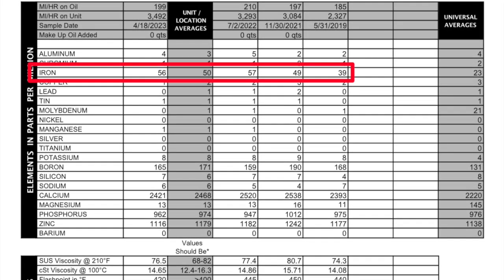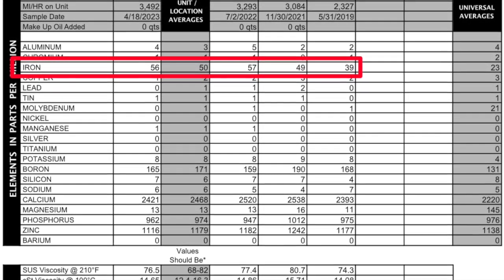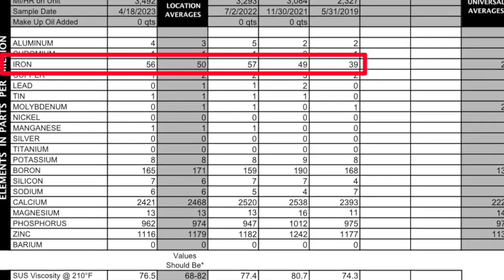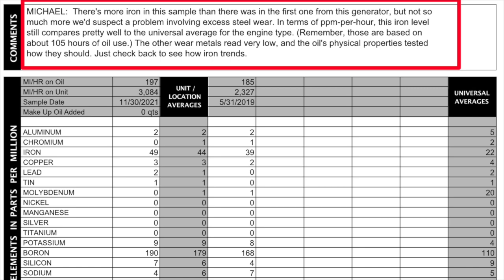I want to switch gears and talk about the Blackstone Laboratories comments and how much I value them, because in situations like this, when I see rising iron levels, I'm concerned. On my November 30th report — the second oil analysis I received — they said: 'Michael, there's more iron in the sample than there was in the first one from the generator, but not so much that we'd suspect a problem involving excess steel wear. In terms of parts per million per hour, this iron level still compares pretty well to the universal averages for the engine type, based on about 105 hours of oil use. The other wear metals read very low and the oil's physical properties tested how they should. Just check back to see how the iron trends.' That helped calm me down a little bit.